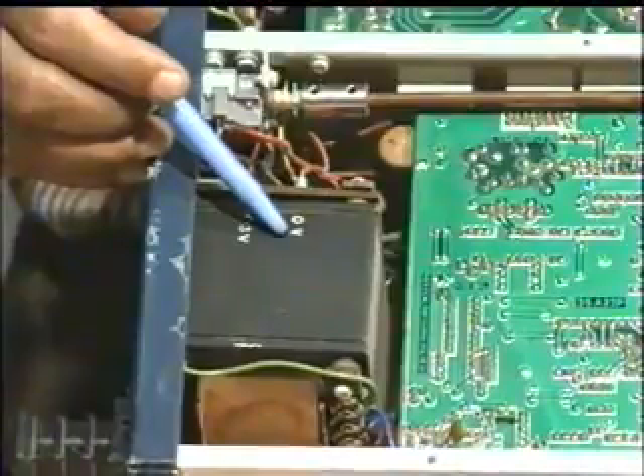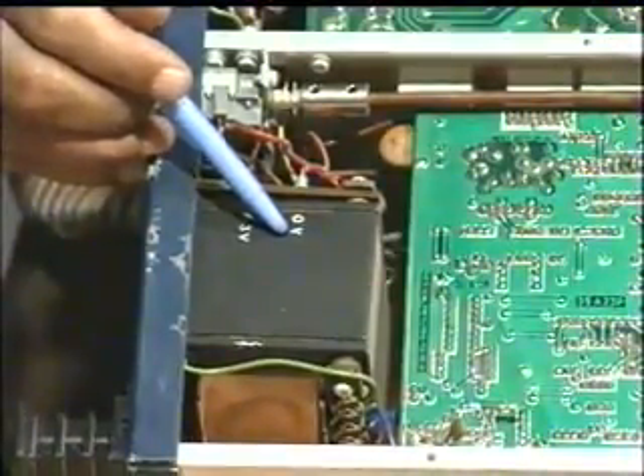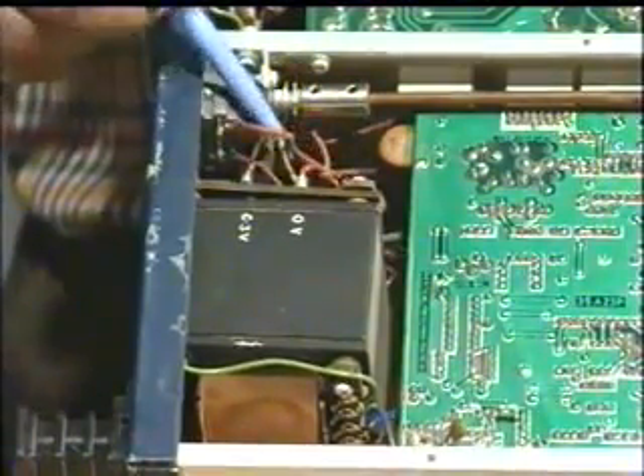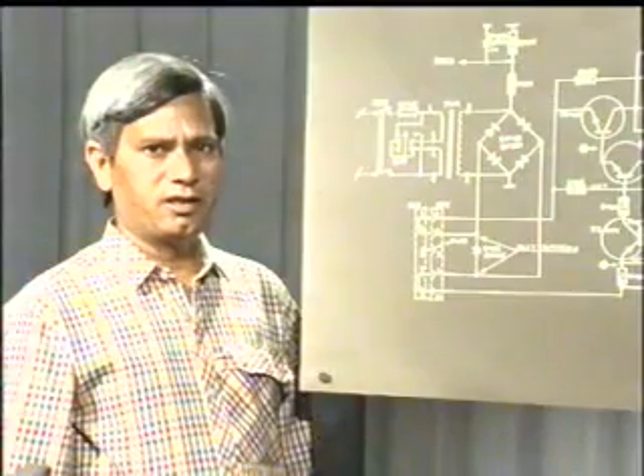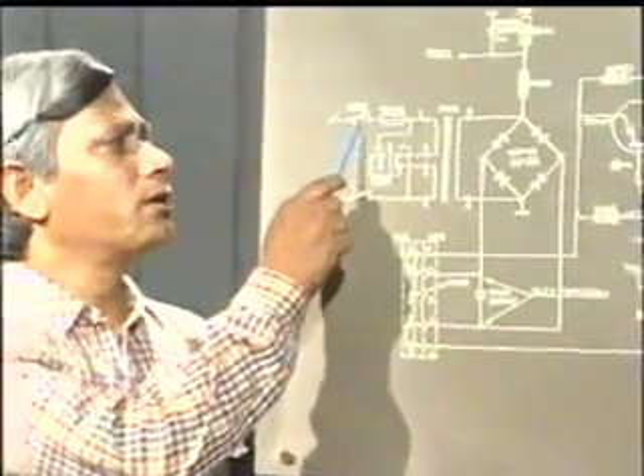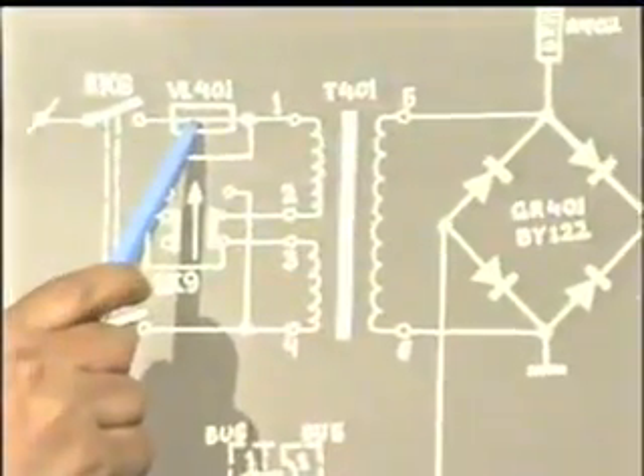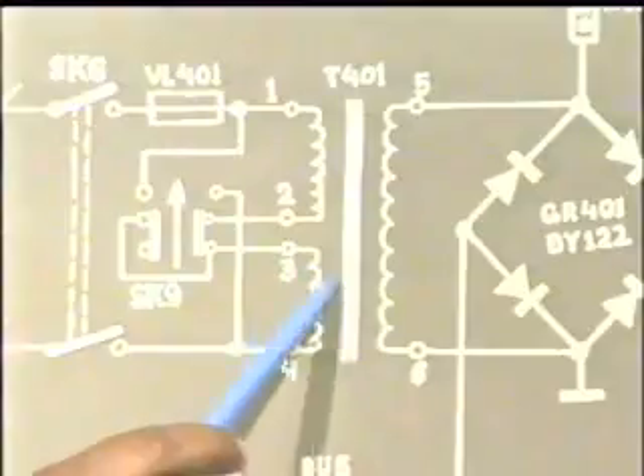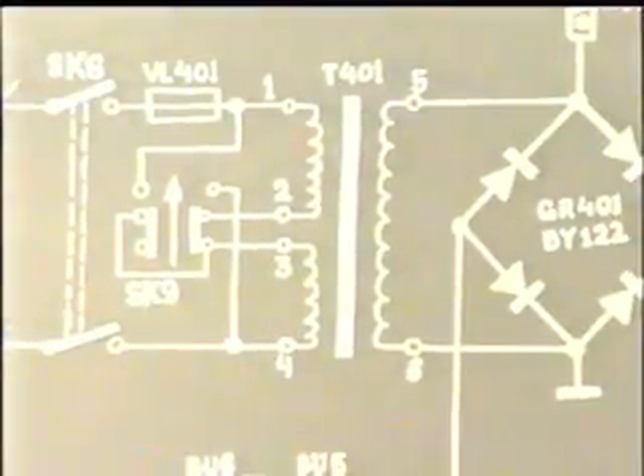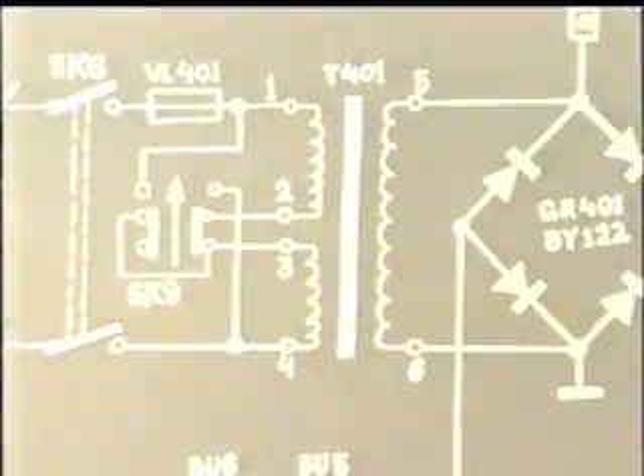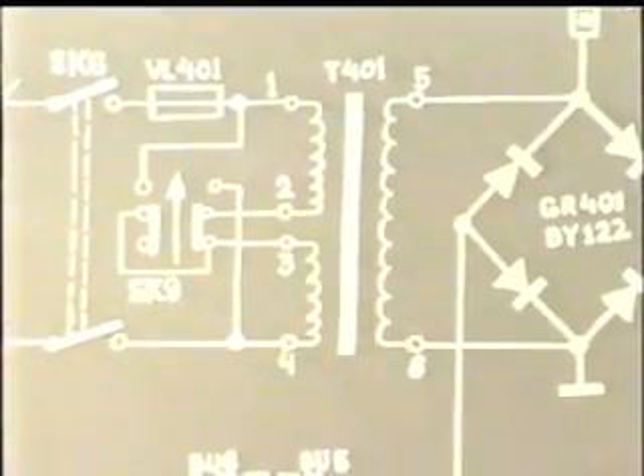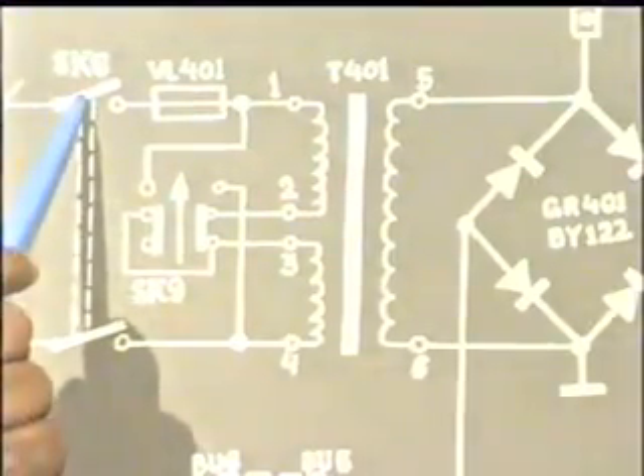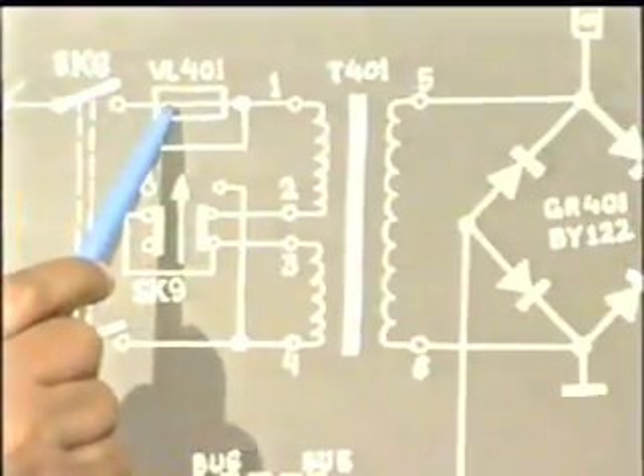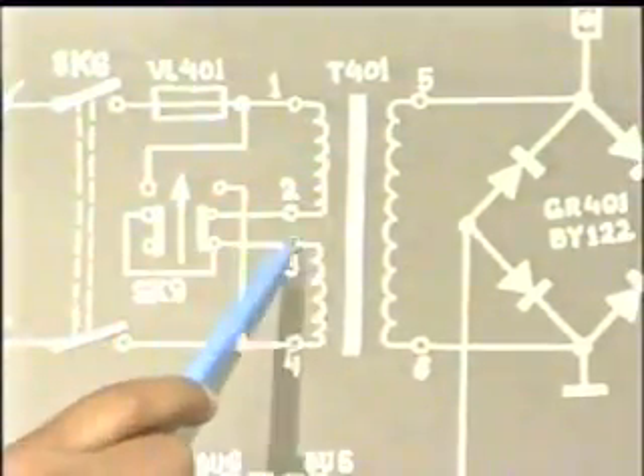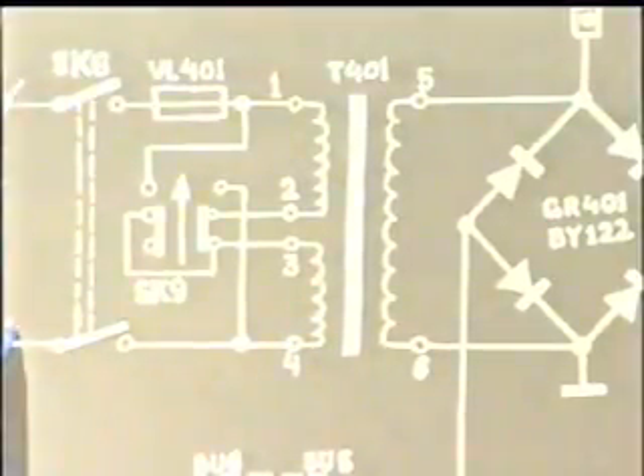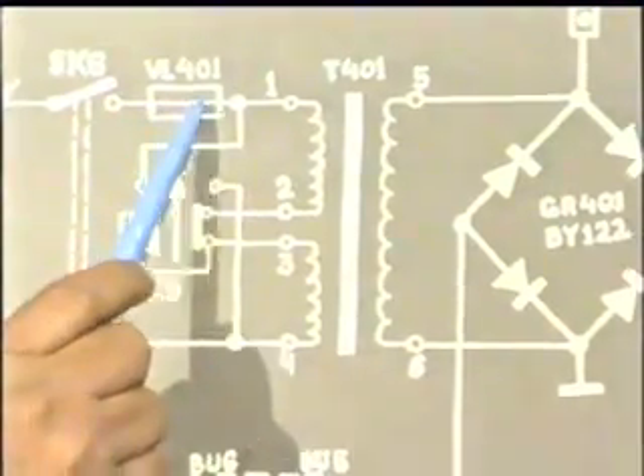This is the main transformer. The primary winding is here, which is connected with the main switch. See in this figure, the main switch, fuse and the primary winding of the transformer are in series. If the symptom is the pilot lamp not glowing, the reason may be an open main switch or fuse or open primary winding. Therefore, check one by one.